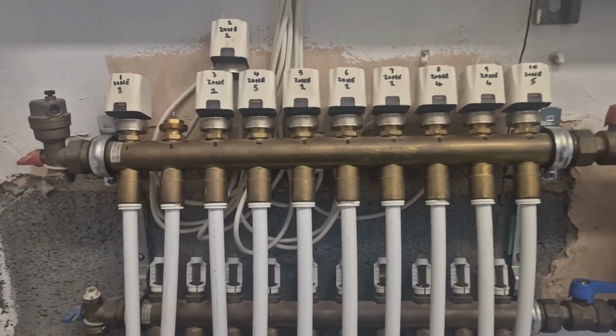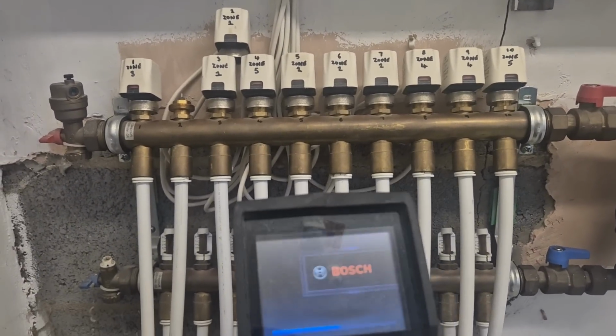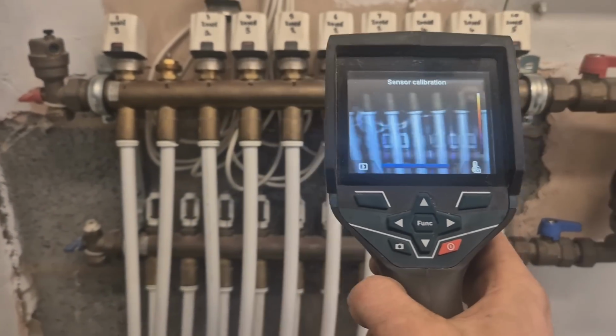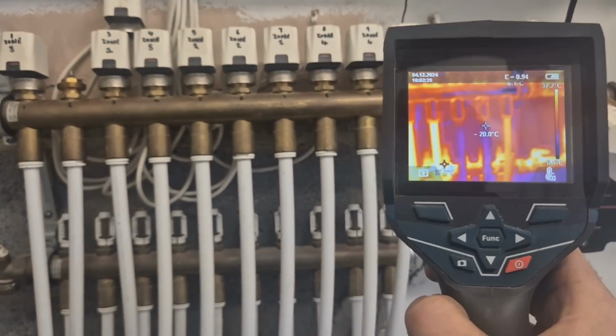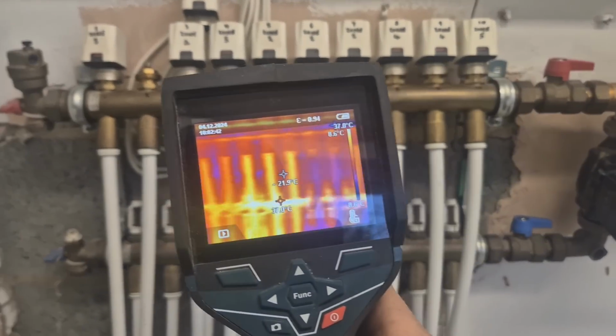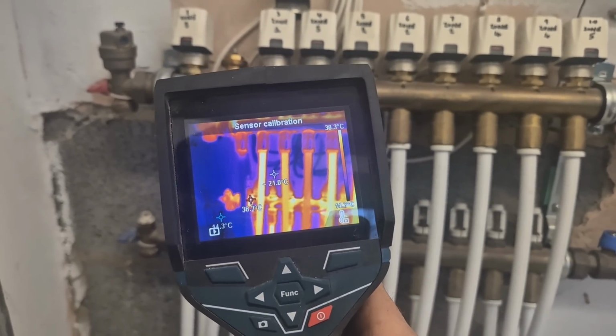Been called to this job. Some of the circuits aren't working on the underfloor heating. I've been around with my thermal camera. Half the rooms are getting hot and half of them cold. I think zone 4 is probably turned off on the stat. I need to go and check. But that loop there too wasn't working.